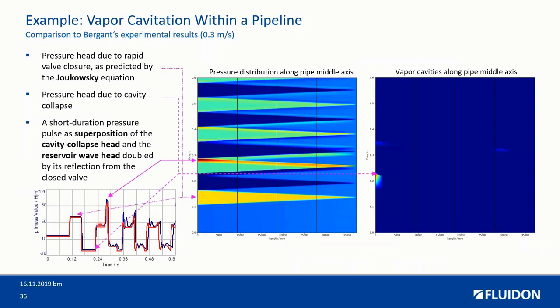Here we see a different representation of what we have just seen as a video. This is the time axis — we march in time like that — and this is the length of our pipes. You see these waves that are formed, these shock fronts travel, they are reflected, they travel back and forth. And here we see basically how these two waves collapse — how they are superimposed. We see the cavitation, the collapse of the cavitation bubble which generates a wave, and the reflected reservoir wave, and how they sum up to form an even bigger wave — way bigger than what you would expect based on simple theoretical analysis.